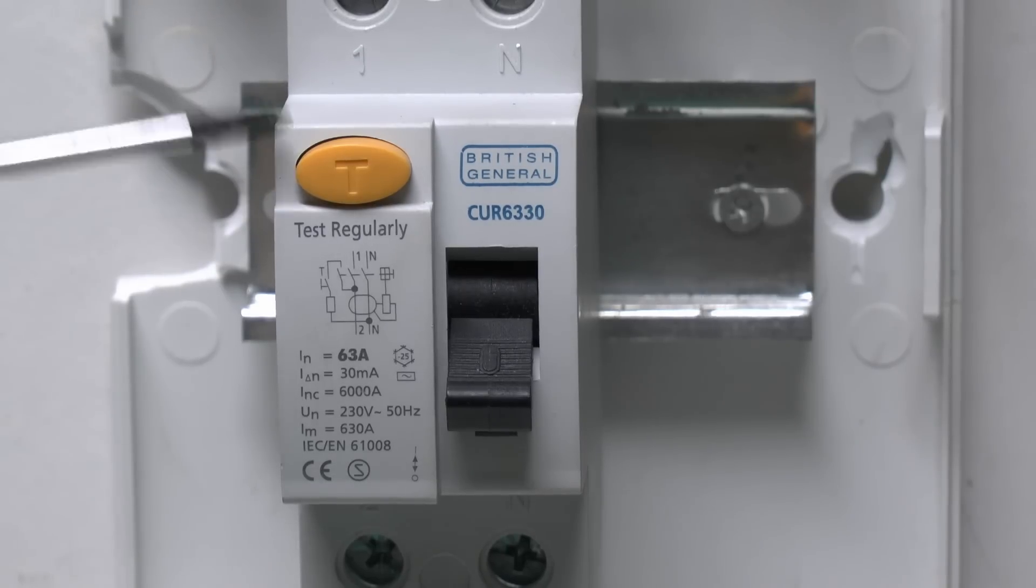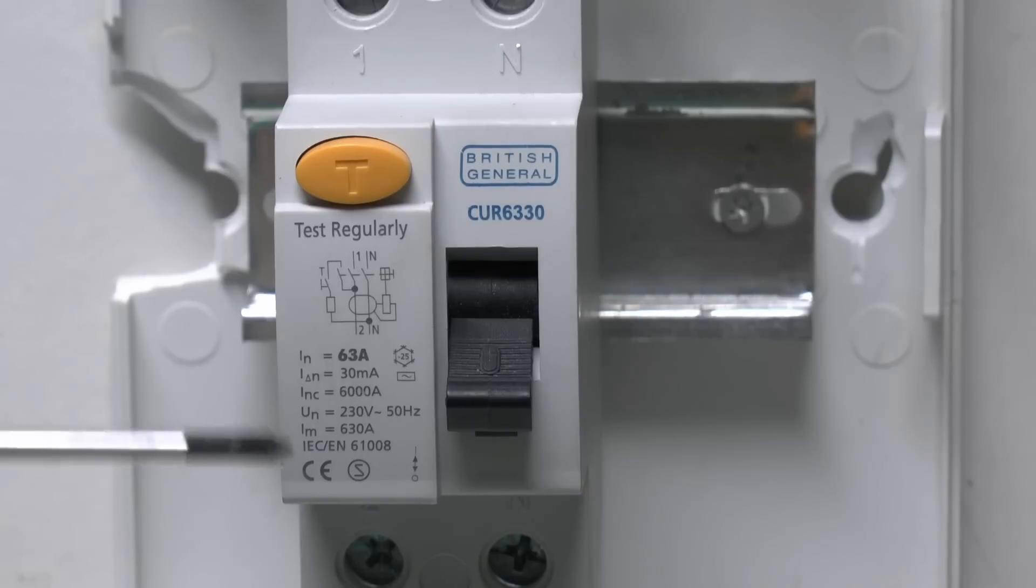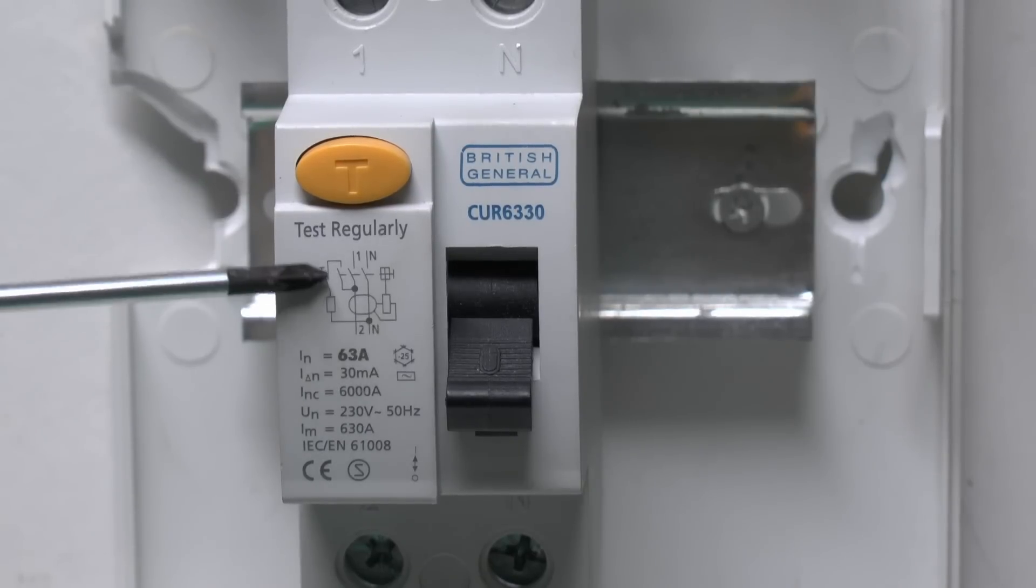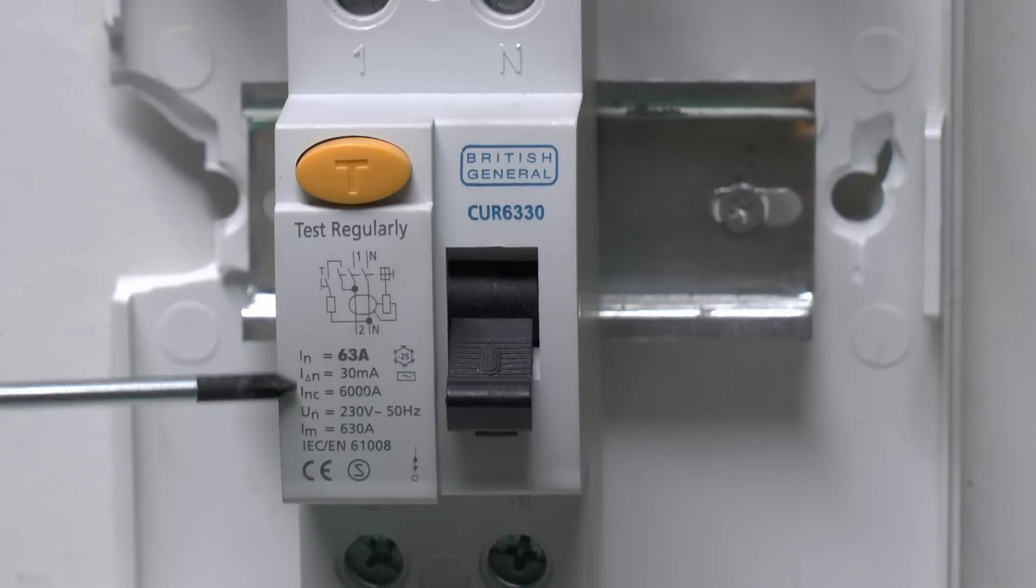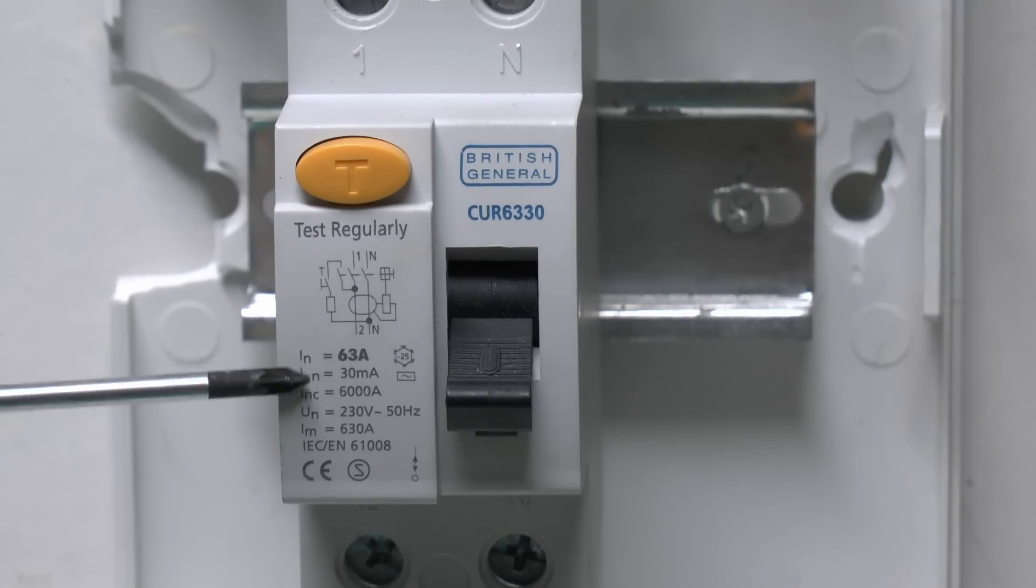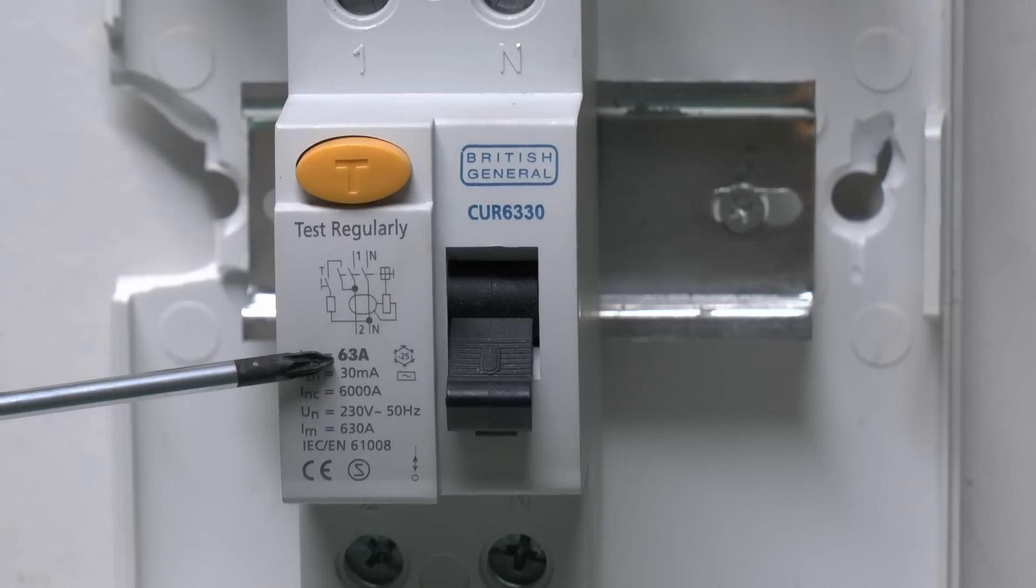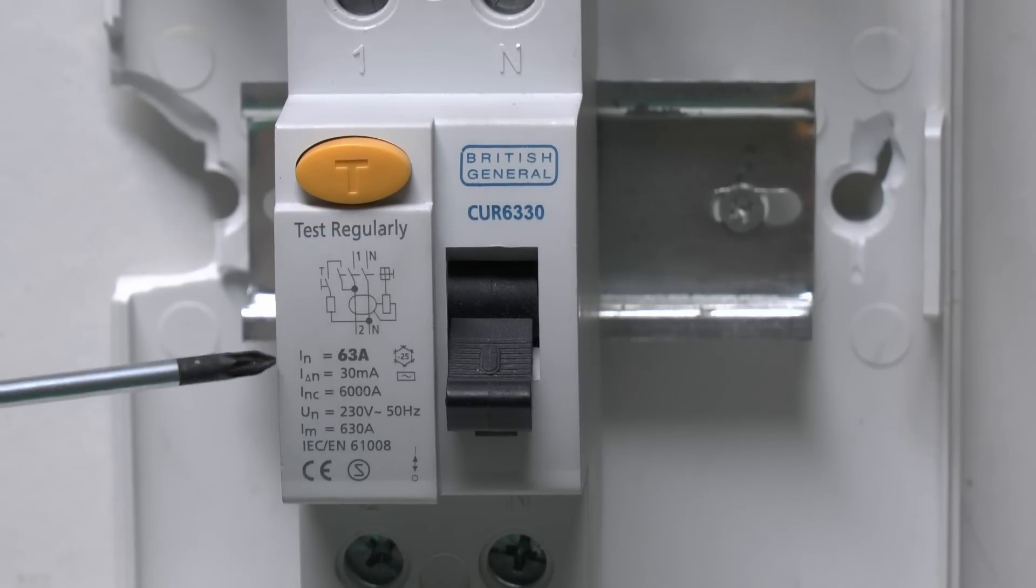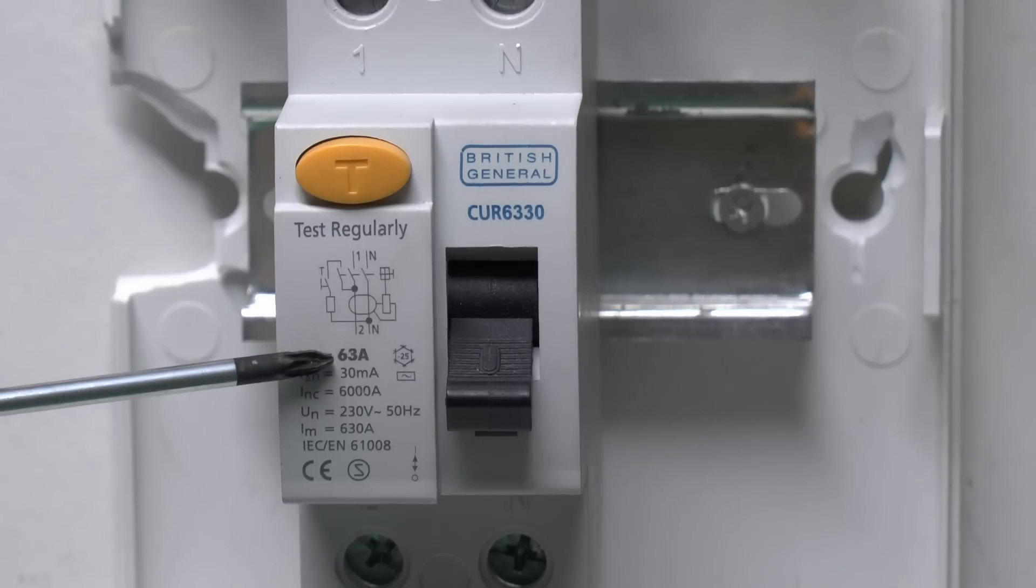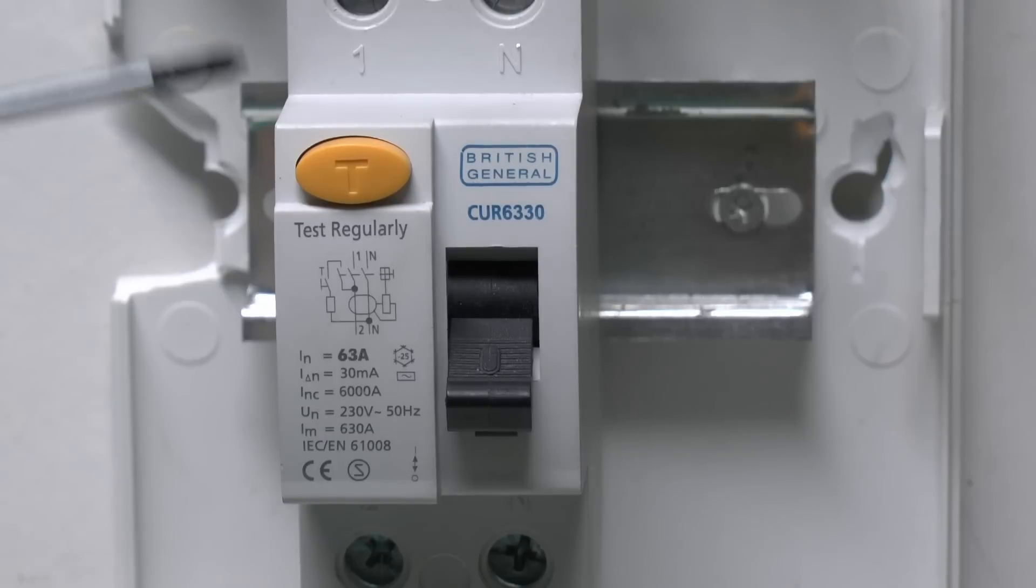Now this particular RCD, as in the case of all of them, has the small test button on here, and underneath here we've got a small diagram showing the sort of wiring layout inside. Then here we've got the various specifications of this device. First of all here we've got the rated current, which is actually 63 amps, and this is not anything to do with any tripping or overload or whatever, it's simply the maximum current that this thing can safely handle. In this case it's 63, and that's really just a function of the contacts inside.